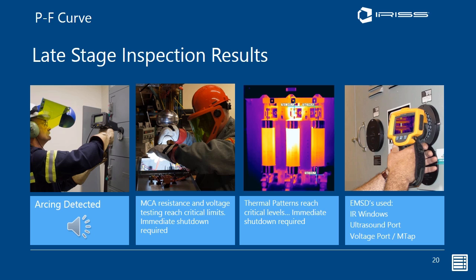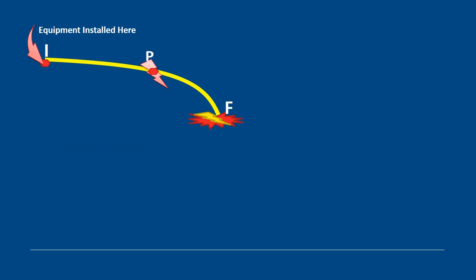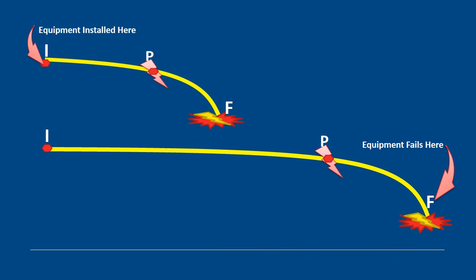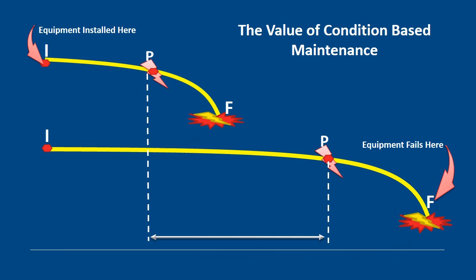So in summary, when we start to look at the PF curve, we can see that when we use condition-based monitoring, we extend the life of our equipment. Using the equipment, we can identify points of failure. Pending failure, we can inspect and repair equipment instead of replacing components. And the extension of that lifetime is really where the value of condition-based maintenance comes in, because we can extend the life of the asset. That gives us a much better return on our investment on the asset and our equipment. And again, much safer methods of working, much better ROI on equipment. So it really is a win-win-win scenario by using condition-based maintenance and EMSDs in our maintenance strategies.